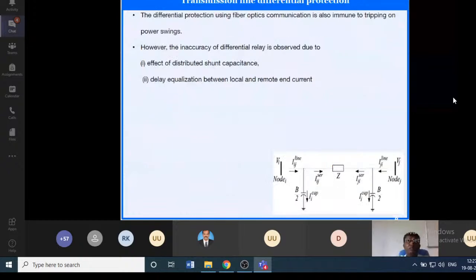Now let us examine another application, in transmission line differential protection. The differential protection can be applied for transmission lines also, with the help of fiber optic cable. The fiber optic cable will transmit the current signal measured at each end to the other, remote end, so that we can compare the currents of the two ends. Then we can apply the differential current algorithm. But the problems associated with transmission line differential protection are the distributed shunt capacitance and the delay in the equalization between local and remote current. So what do I mean by that?